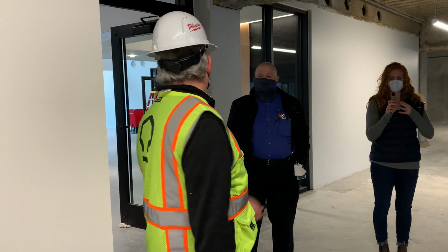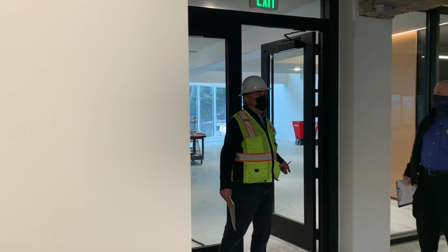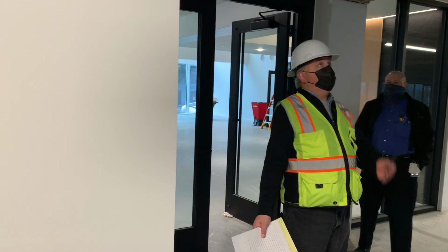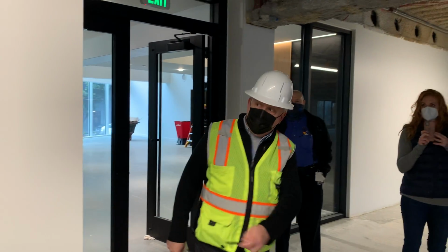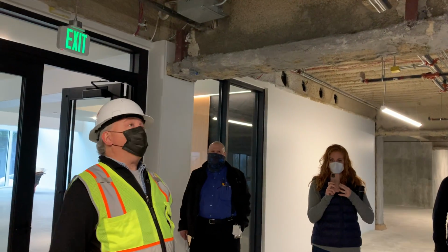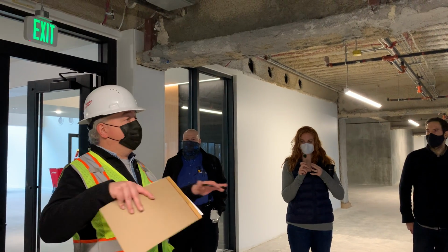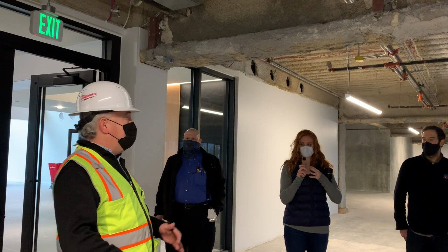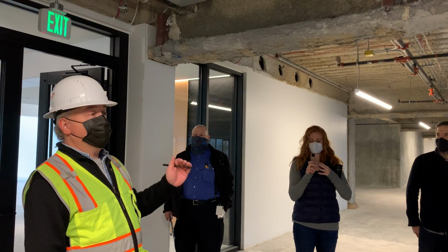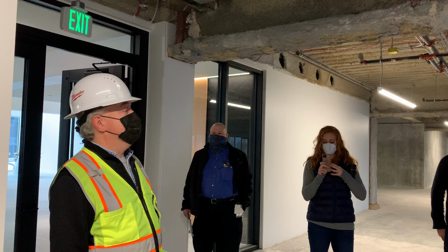So they'll be located in places where you'd be coming out of the interior core or stairwells and out into the empty space. You'll find a sensor basically right outside the stairwell, and one here outside where the lobby enters into this space, similarly on the other side. And the occupancy sensors trigger just the floor that they're on. So where the time clock sweeps all levels 5, 6, and 7 on, the occupancy sensors only trigger the floor on which they're located.